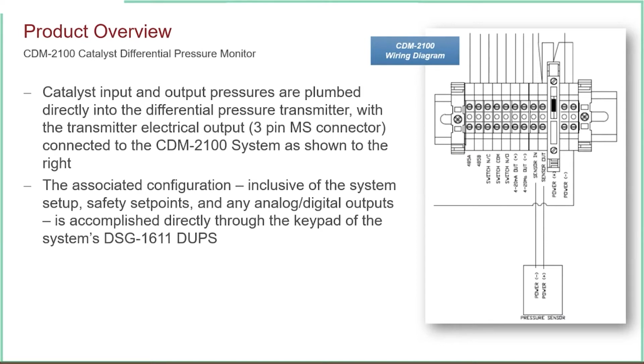On the right-hand side here, you can see your power connections, your sensor in, sensor out, which would go to the DP transducer. But you've also got a 4 to 20 out from the DSG 1611. So if that information needed to be sent over to a PLC or some other device, you do have a 4 to 20 out if needed. And that's fully adjustable. We're programming it to be 4 to 20 out from negative 14 to positive 14 inches of water column, but we all know you can make that 4 to 20 do whatever you want with the micro inside of the DSG 1611. So that 4 to 20 may be needed in some applications for PLCs or other information.